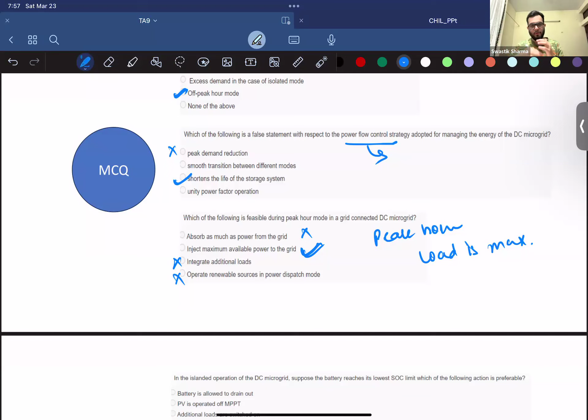You don't want to integrate more loads, and you want to operate renewable sources in power dispatch mode. No—all of your renewables will be at MPPT, meaning they're not dispatchable. Whatever power they produce is injected into the grid so that all available generation is utilized during peak hour.